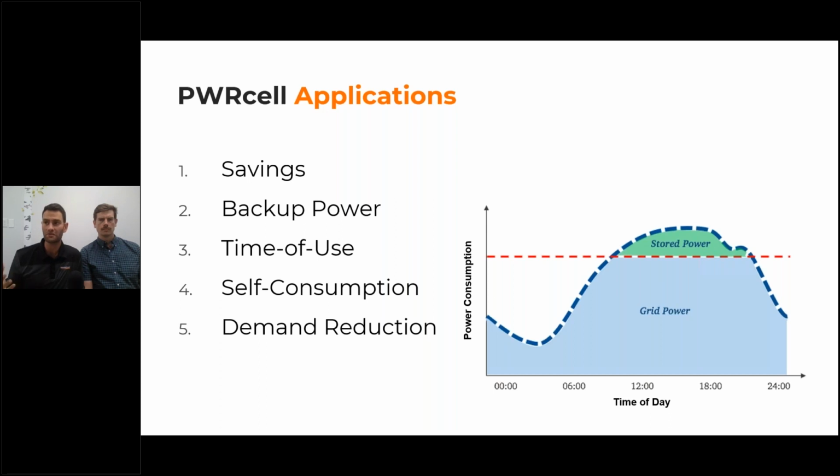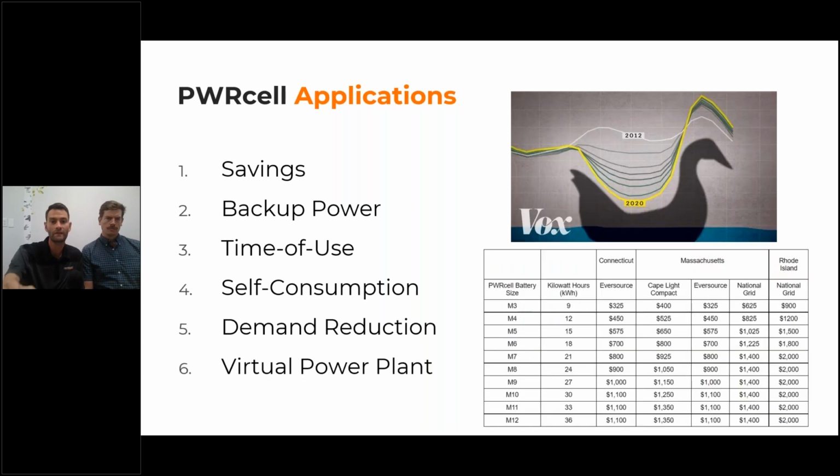There are a few markets where residential demand charges are applicable, like I believe in APS. And so built into the inverter out of the box, we have a set point called max import power, max import P. And so what you can do is basically set the inverter to discharge the battery if and only if there's an outage, or if the house starts to consume a certain amount of continuous electricity. So once the house hits 4,000 watts, we'll start to discharge the battery to essentially cover any power consumption above that 4,000 watts. And again, this is a pretty cool functionality that we have right out of the box, leveraging the current transformers that we ship with our equipment.